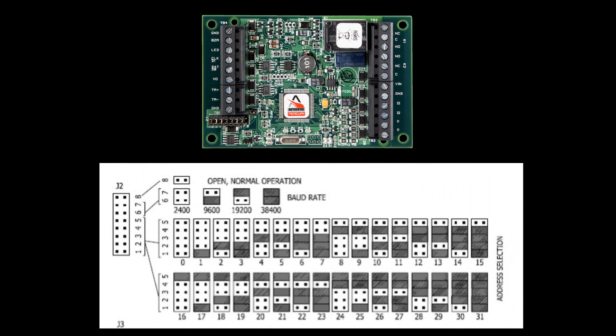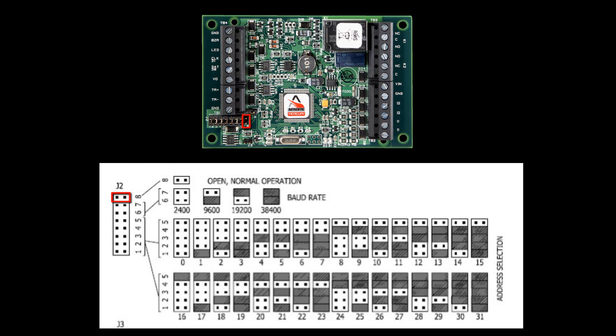All Mercury sub-panels like the MR50 and MR52 must have a unique physical address when connected to the same RS485 bus. On the MR50, the addressing is done on the J2 jumpers. Jumper 8 has to be open for normal operation. Jumper 6 and 7 are for the baud rate. Both 6 and 7 have to be jumped to match the Genetec default settings.